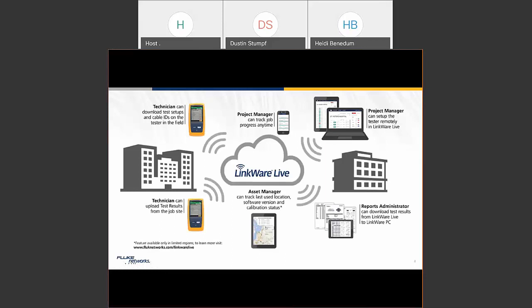LinkWare Live is a cloud-based solution that allows you to manage your testers, your results, and your setups — everything to do with the testing process. The project manager can set up all the testers remotely, logging in to set up tests, label IDs, and uploading that to the cloud. Technicians in the field then download those test setups and cable IDs into the tester, do all their testing, and upload results back to the cloud. The project manager can monitor project progress at any time from a laptop, tablet, or phone.